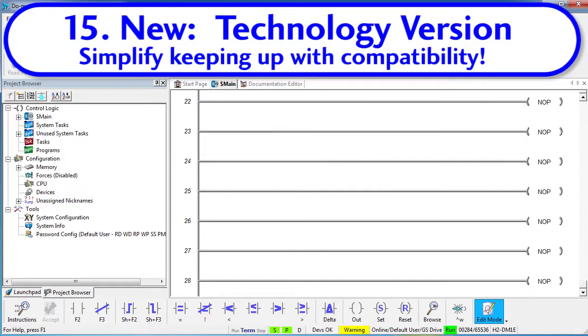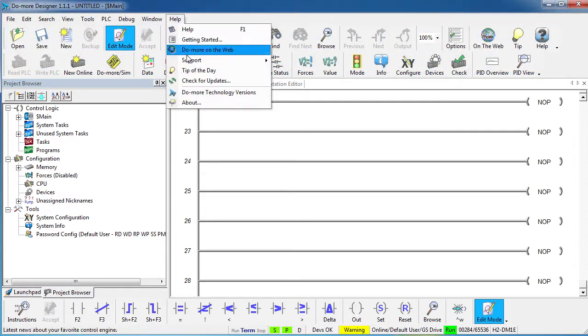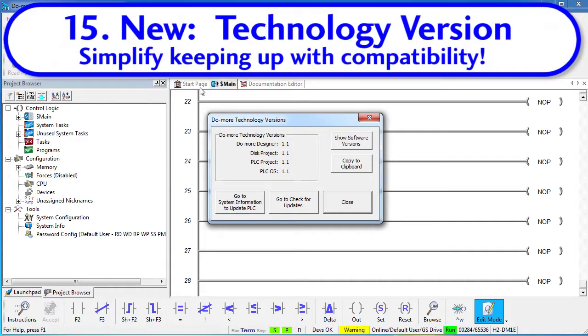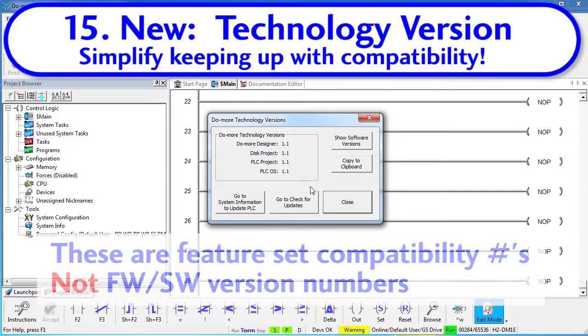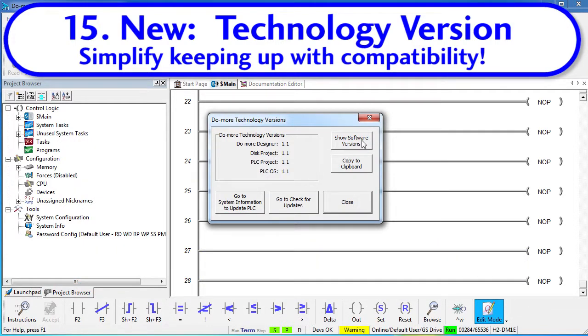You know what a pain it can be to keep up with which software is compatible with which firmware, with which hardware, with which bootloader. Well, with the new Do-More technology version, all of that goes away. At a glance, you can now see which features are supported by which technology. For example, suppose this says my PLC OS is 1.0 — that means it can only support technology version 1.0 features. It's okay to use Do-More Designer at technology version 1.1; you just can't use those advanced features in a 1.0 device unless you upgrade the firmware. These are NOT firmware or software revision numbers — they are feature set numbers, so don't confuse the two. If you want to see the actual firmware and software versions, just click on this button right here.